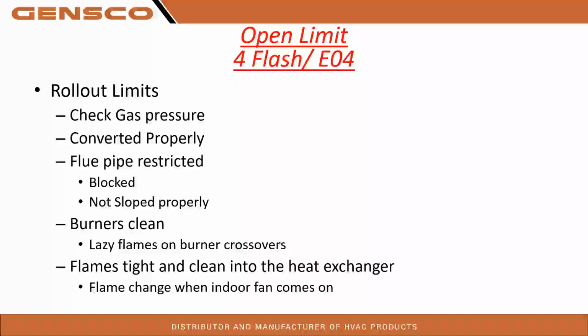So when we get into heat exchanger checking and customer concerns, we always want to go to the return first and pull the CO number from the return. It could be something else in the space. Could be the water heater, natural draft water heater not drafting properly. Could be a cooking situation within the home. So we're always going to check everything, right? We're really going to break it down.